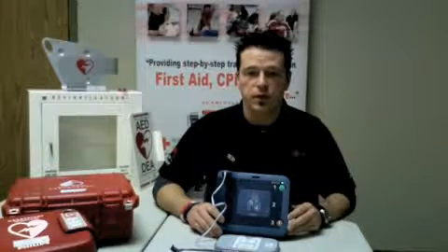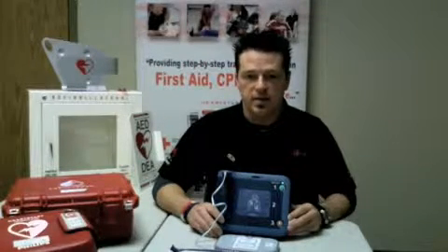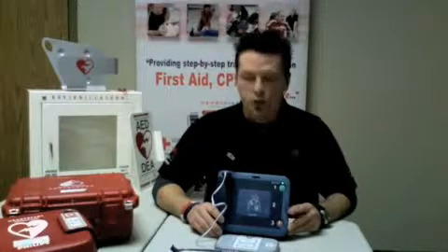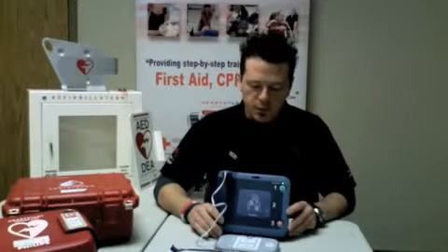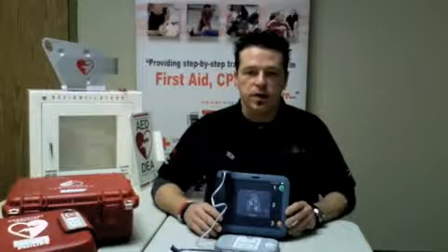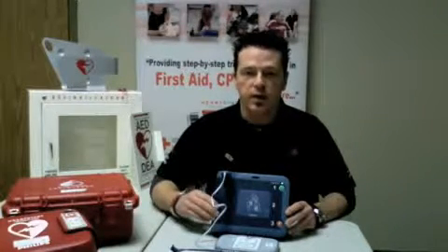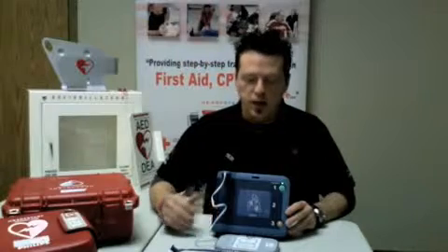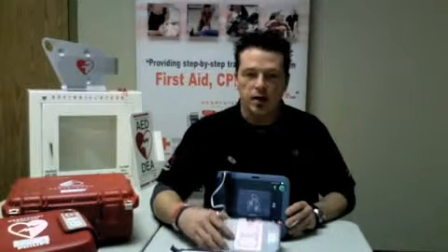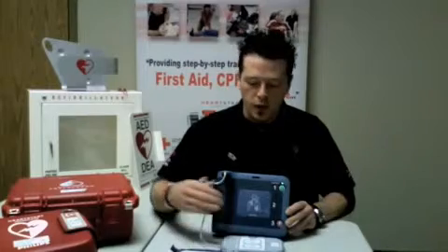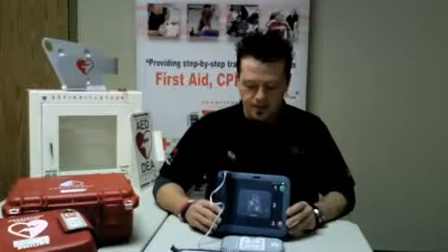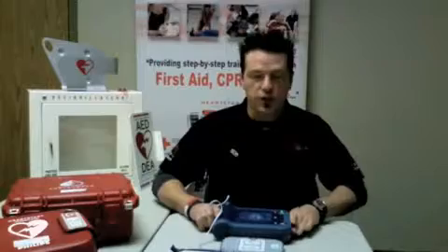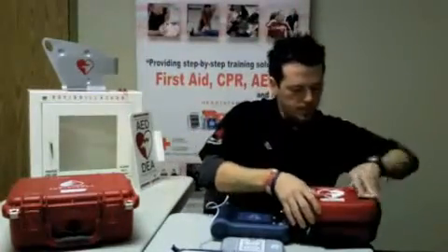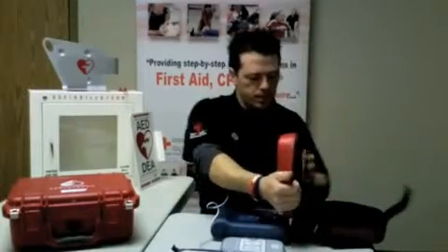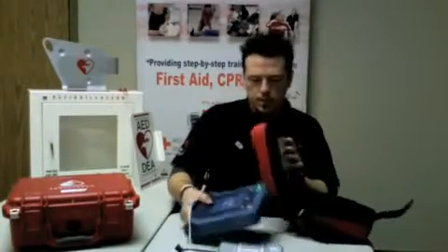Having pressed those two buttons, the machine will start to keep repeating testing, testing, testing, and we'll do so for about a minute. Now, the reason for this is that it's checking its capacitors to make sure that the defibrillator can deliver the electrical shock if required, and is making sure that the adhesive gel and the consistency is working. You'll hear some clicking coming from the defibrillator. And from this point on, we're just going to let it finish. Testing. Ready for use.